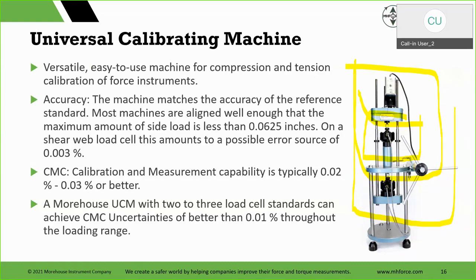CMCs, typically 0.02 to 0.03. Most customers, when they come to our training or go to our training course or we help them out, they do the repeatability test, they do everything else, reproducibility. They do all of these tests and then they end up with a CMC, depending on where it is, typically between 0.02 and 0.03. And then a Morehouse UCM with 2 to 3 load cells can achieve CMCs of better than 0.01% throughout the loading range.